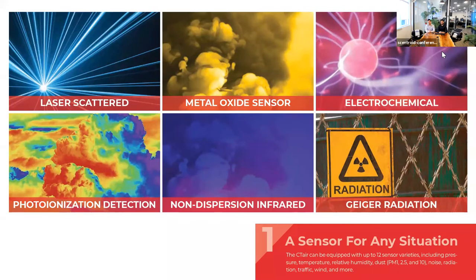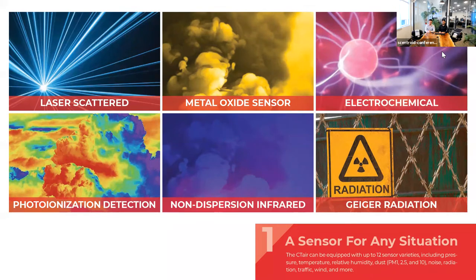We utilize many different sensor technologies to get the best accuracy and results. Laser scatter technology is used for high-accuracy measurements of particulate matter — we measure PM1, PM2.5, PM4, and PM10, with an option for total suspended particulates. We also use metal oxide sensors for different chemical gases. For measuring a broad range of VOCs, we use photo ionization detection. For CO2 or CH4, we use non-dispersive infrared (NDIR) technology. Most of our chemical sensors use electrochemical cells. Depending on your application, we study these technologies and recommend the combination that will work best for you.